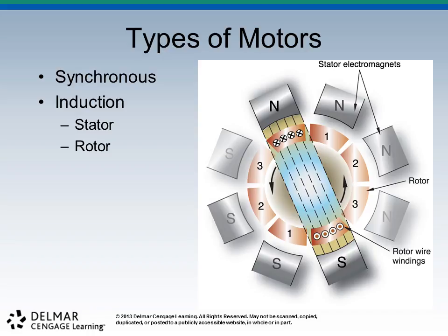Okay, but you'll notice on the outside of that X-ray tube that there's some really heavy magnets, and you see these out here in the illustration, and we call that the stator, which is outside the X-ray tube. So the rotor is inside the glass part of the X-ray tube, and the stator is actually the big heavy magnetic stuff with copper wrapped around it, which is outside the X-ray tube. And those two work in concert.